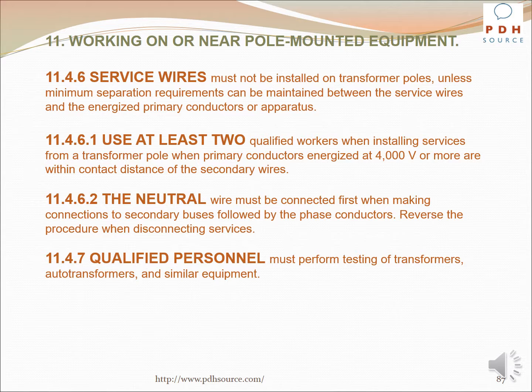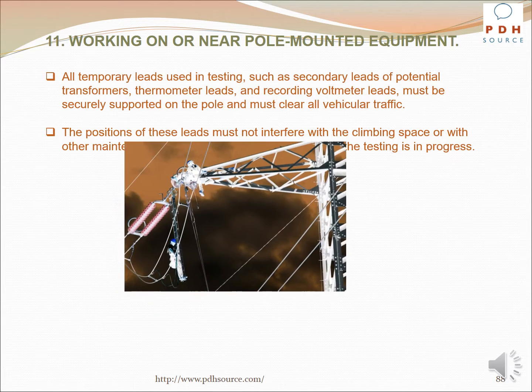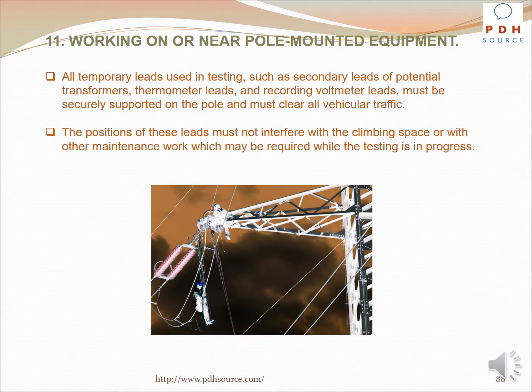Qualified personnel must perform testing of transformers, auto transformers, and similar equipment. All temporary leads used in testing, such as secondary leads of potential transformers, thermometer leads, and recording voltmeter leads, must be securely supported on the pole and must be clear of all vehicular traffic. The positions of these leads must not interfere with the climbing space or with other maintenance work which may be required while the testing is in progress.